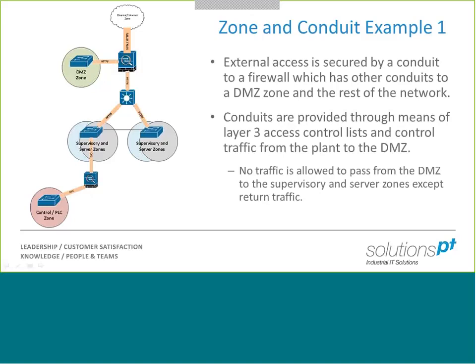We're making use of a secure protocol here, HTTPS, and imagine we're using one of the later SCADA packages that makes use of that and is able to offer a lot of functionality through a web browser. So we've got HTTPS allowed through there to our supervisory and server zones. Perhaps we've got web servers there, so from our server zones we may need to access a web server in a DMZ, but nothing else is allowed through, so there are no devices here with outbound internet access.